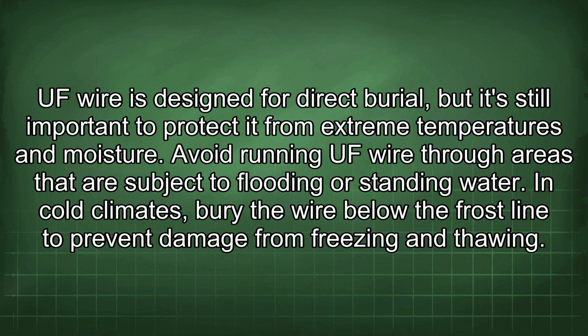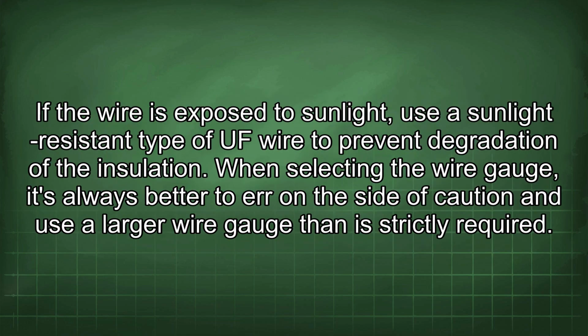In cold climates, bury the wire below the frost line to prevent damage from freezing and thawing. If the wire is exposed to sunlight, use a sunlight-resistant type of UF wire to prevent degradation of the insulation.